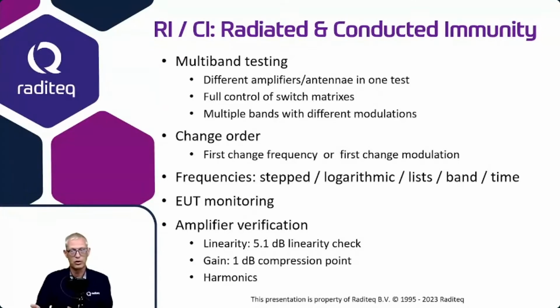With the change order, an end user can decide if he first would like to change the frequency, where all the frequencies are tested, and then the next modulation is activated and all frequencies are tested, and then finally the pulse modulation is activated and all the frequencies are tested.